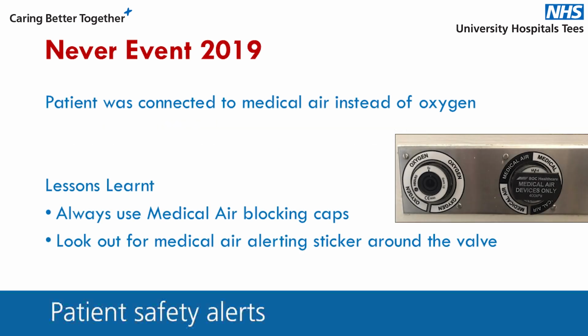Administration of air via an air flow meter was discontinued in 2019. If air is administered in error instead of supplemental oxygen, this is now classified as a never event. Blocking caps are now inserted into the piped medical air outlets to minimise this risk relating to human error. If there is a clinical need to use the piped air via flow meter, this must be removed from the outlet after use and stored away and the blocking cap to be reinserted.